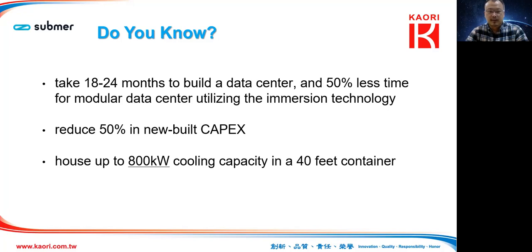One interesting observation I have for air cool container data centers is that I believe the maximum you can reach is 300 kilowatts of cooling. But with immersion cooling technologies, you can house up to 800 kilowatts in cooling capacity. That means more cooling for the modular data center, and in another way, more reusable heat for the data center.